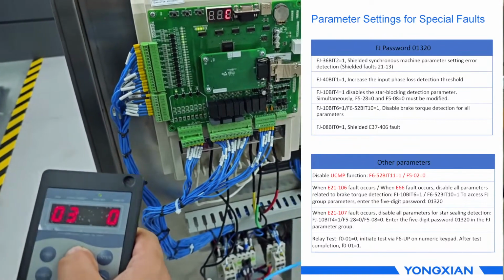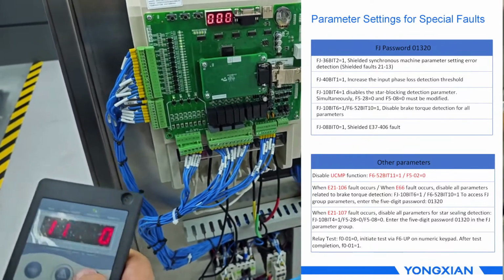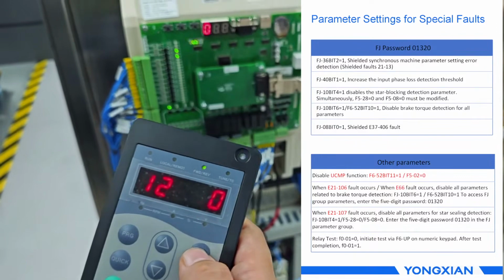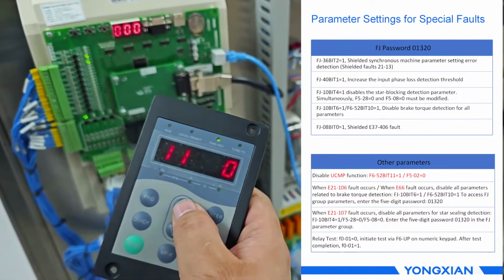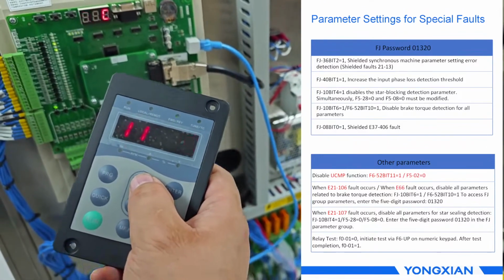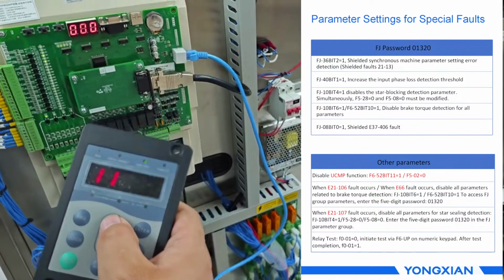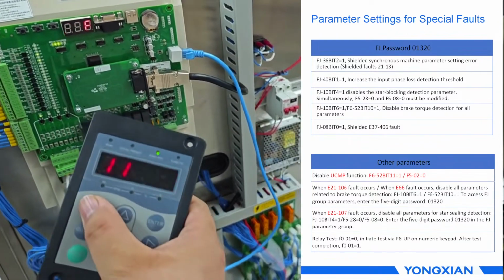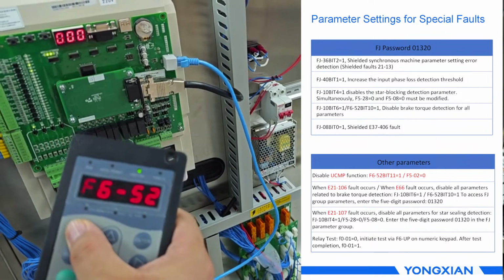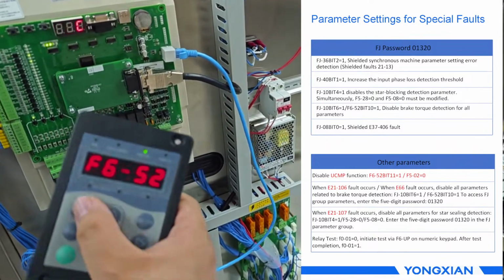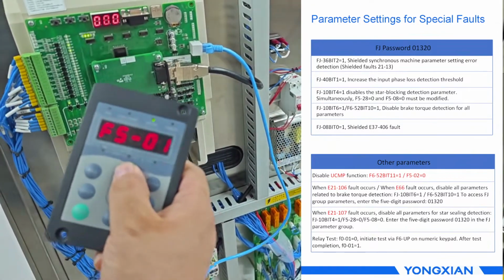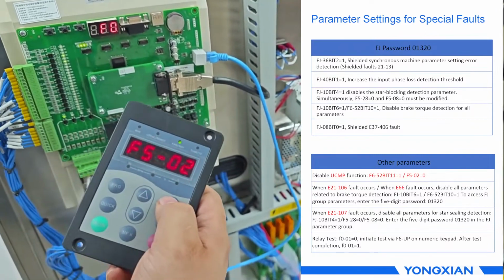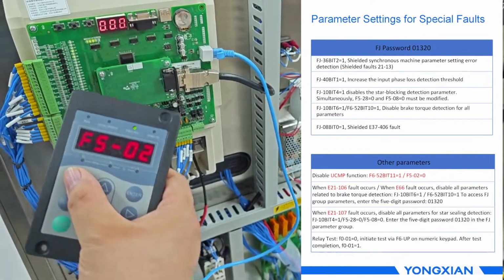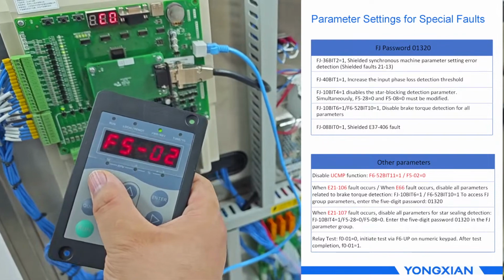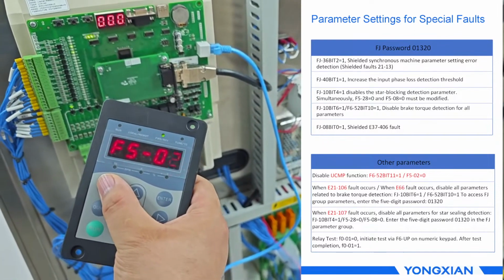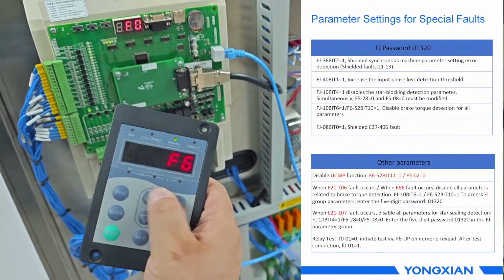F6-52的 bit 11。F652 bit 11 equals 1. 设置成1是关闭我们的 UCMP 功能。When set to 1 it disables the UCMP function. 相关的我们 F5-02 也要设置为0。The relevant parameter is also required to change. F502 also needs to be set to 0.